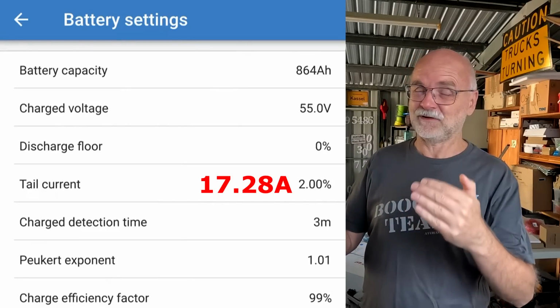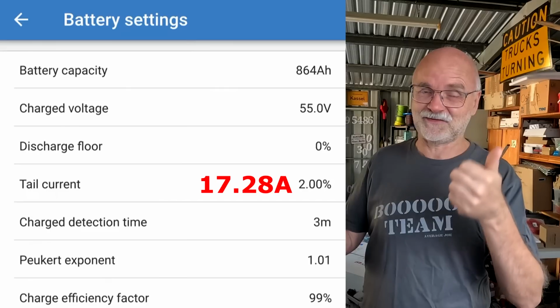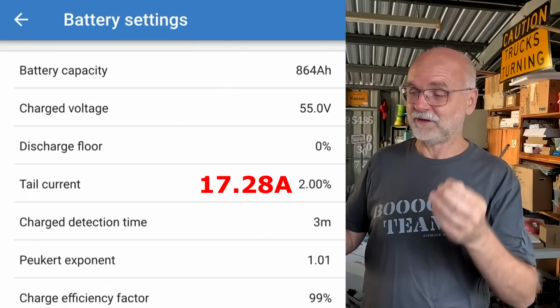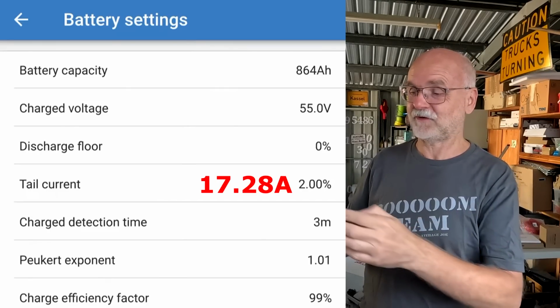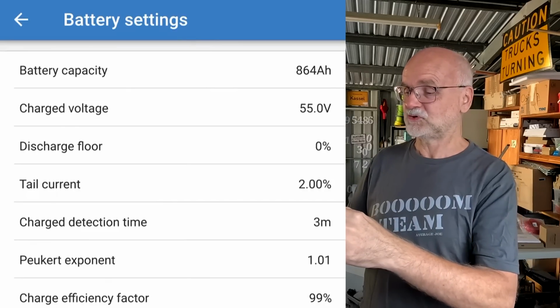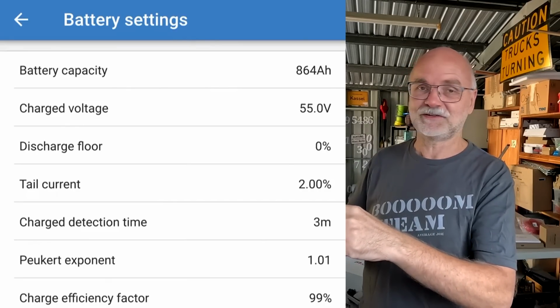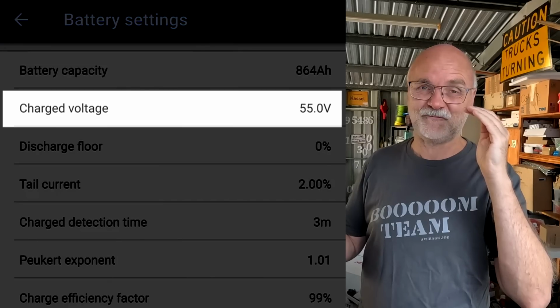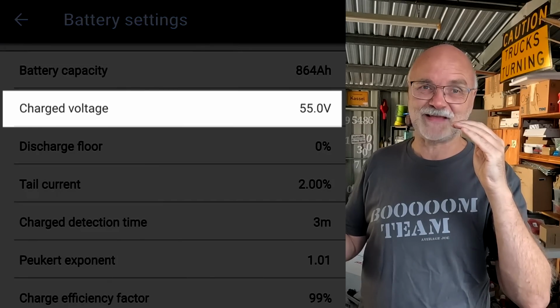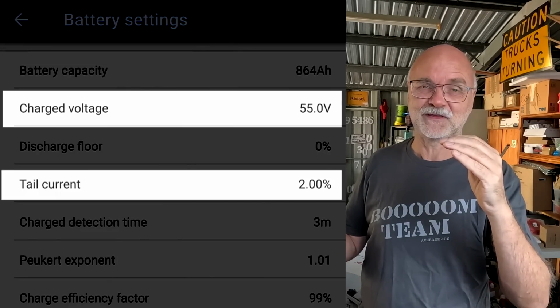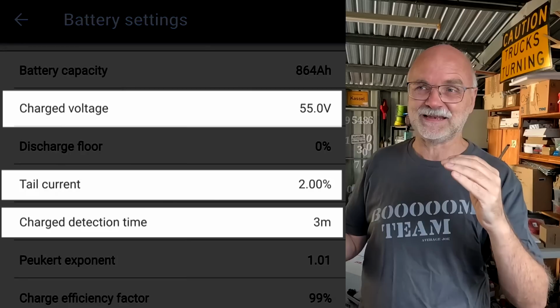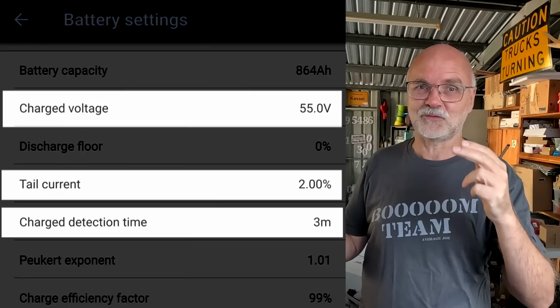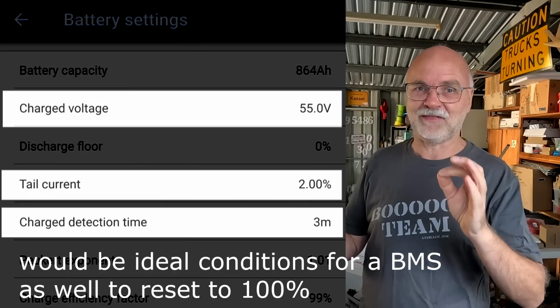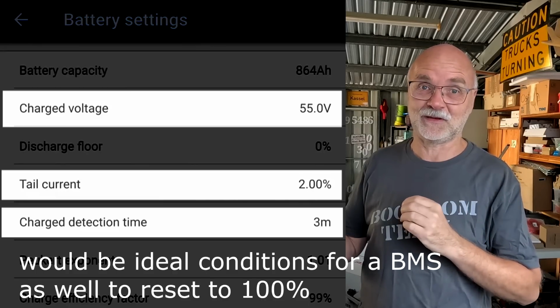So if the tail current is under 17 amps, that's another criteria for the Smart Shunt to reset to 100%. But there's a third one, which is the charged detection time. So we need to be at 55 volts, current under 17 point something amps, for at least 3 minutes. Only if these 3 parameters are true will the Smart Shunt show 100% state of charge.